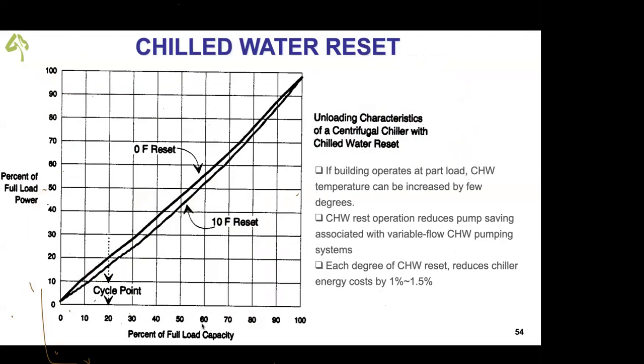Then another way of reducing energy is chill water reset by BMS. We raise the chill water temperature in part load conditions, especially part load, not full load conditions. That directly reduces the building energy demand. Each degree of chill water reset reduces chiller energy consumption by 1% to 1.5%. How do you do that? The chiller operates at 7 degrees C, return 12 degrees C. Chiller out 7 degrees, we will raise 1 degree to 8 and go to 9 degrees and watch. But this is done during part load.